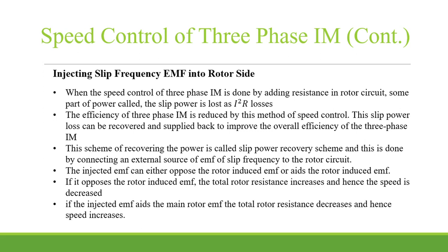In order to improve the overall efficiency of the three-phase induction motor, if we supply back this power which is lost, then this is known as injecting the slip frequency EMF into the rotor side. Now how will we recover that power? By connecting some external source of EMF of slip frequency to the rotor circuit. That injected EMF in the rotor side can either oppose the rotor induced EMF or add to the rotor induced EMF. So we get two options.